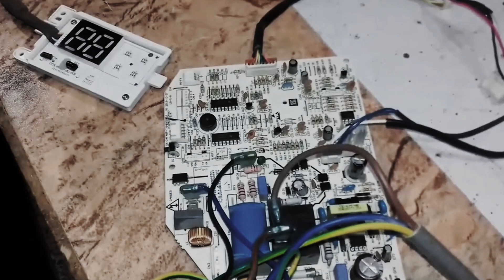I will turn on the power, and as you can see, the E4 error has appeared on the display. This means there is a feedback error from the fan motor of the indoor unit. Currently, I have disconnected the motor from its connector, and that is why it is showing the E4 error. However, if this error appears on your unit, it indicates that the fan motor is faulty.